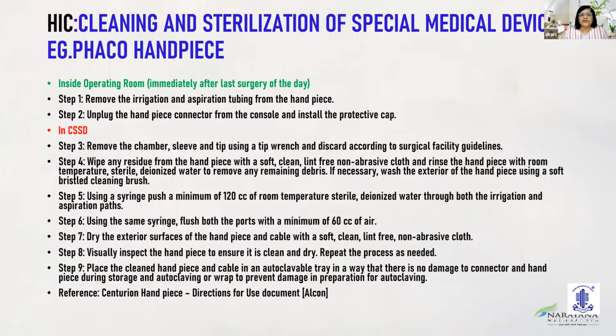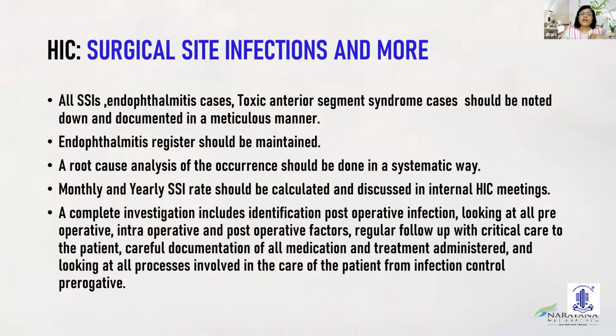You will wipe off any residue from the handpiece with a soft, clean, lint-free, non-abrasive cloth. Use a syringe to push a minimum of 120 cc of room temperature sterile deionized water. Use the same syringe to flush both the ports with a minimum of 60 cc of air, and so on and so forth. So basically what I want to say is that the protocols for these reusable special medical devices should be very much in place. Now, SSIs, we have spoken about it.